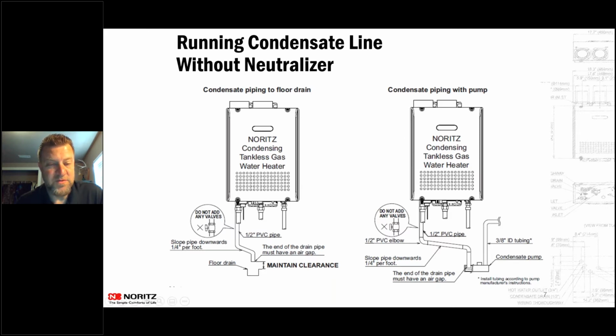Also, do not put any valves in that line coming out. We don't want any kind of bottleneck in that drain as it's draining out using gravity. Just like any other appliance, whether it's a water softener or whatever you're running to that floor drain, there must be an air gap. So make sure that when you're running that down, you're running it not inside of the drain, but outside of that drain, so there is that gap in between. We require on our units a 1/4 inch per foot grade from the unit down to that floor drain.